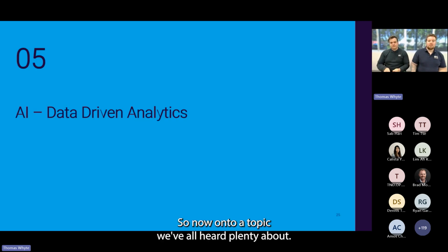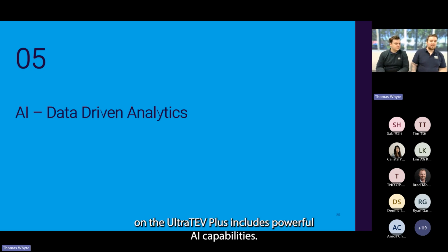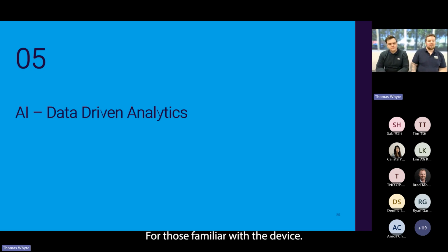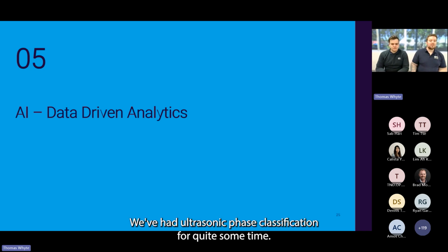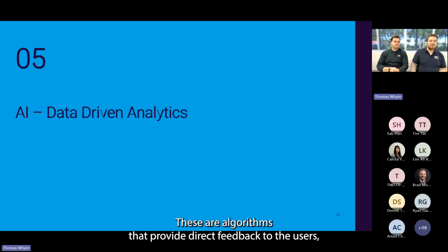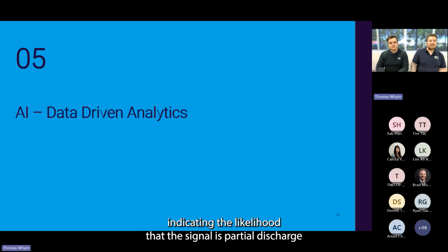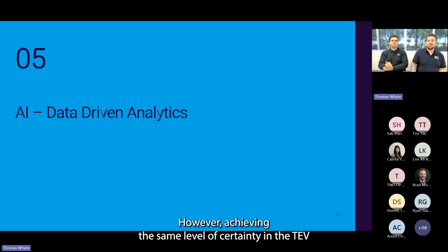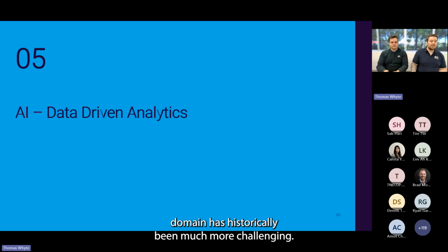So now onto a topic we've all heard plenty about. We're excited to announce that the latest firmware update on the UltraTEV Plus includes powerful AI capabilities. For those familiar with the device, we've had ultrasonic phase plot classification for quite some time - algorithms that provide direct feedback to users, indicating the likelihood that a signal is partial discharge or electrical noise. In the ultrasonic domain, this classification has proven highly reliable. However, achieving the same level of certainty in the TEV domain has historically been much more challenging.